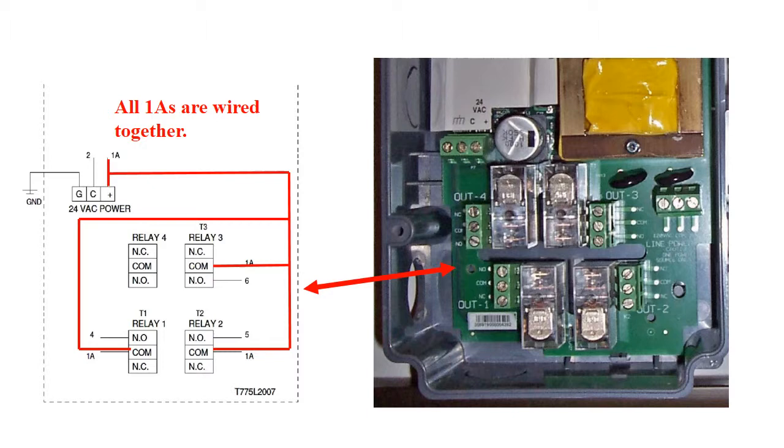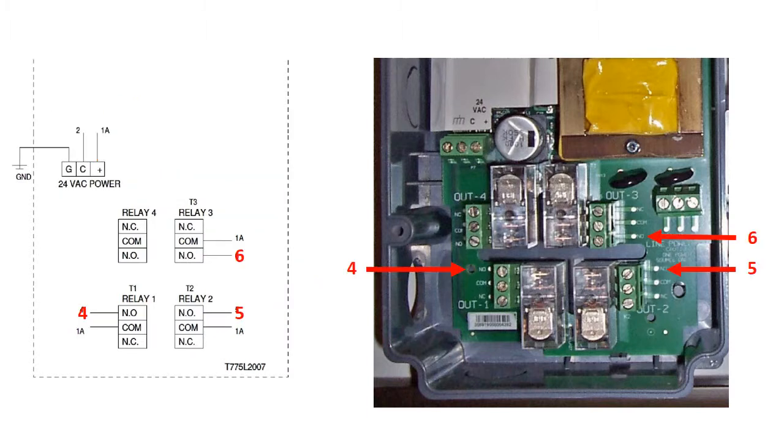Relay number 4 is not used in this installation. Next to the COMs are normally open terminals with the numbers 4, 5, and 6, which indicate the corresponding terminal connections on the dehumidifier as mentioned earlier. Be certain that you are on the normally open, or in some cases normally closed terminals, as indicated on the schematic for your installation.